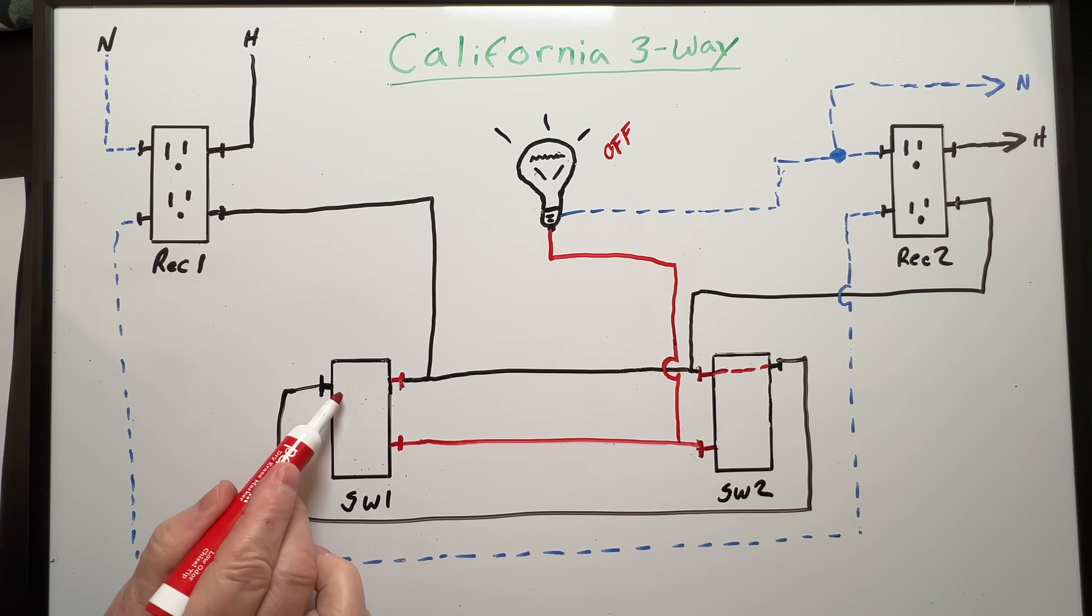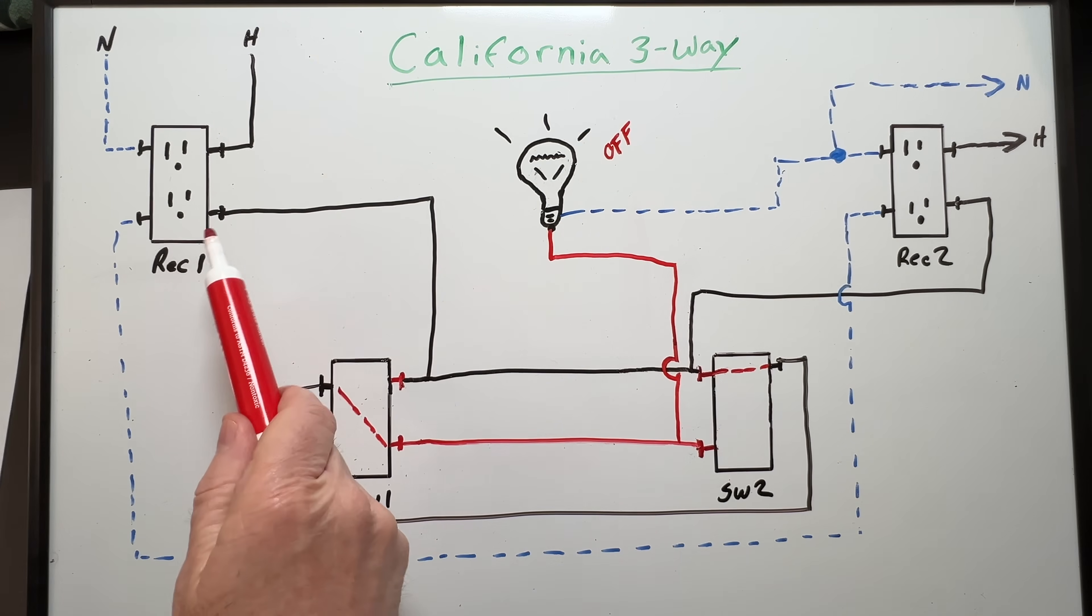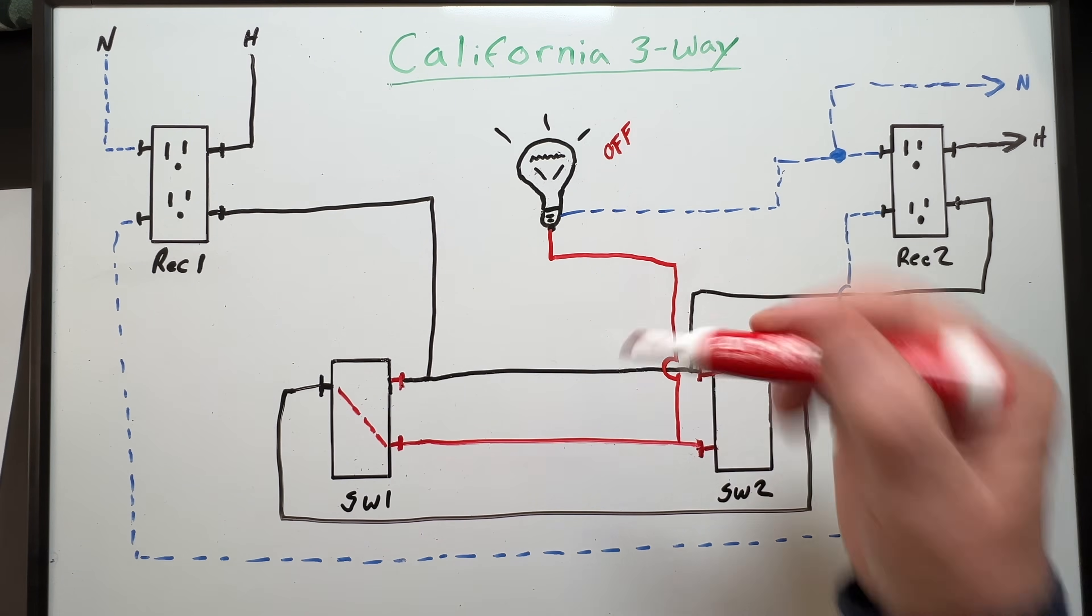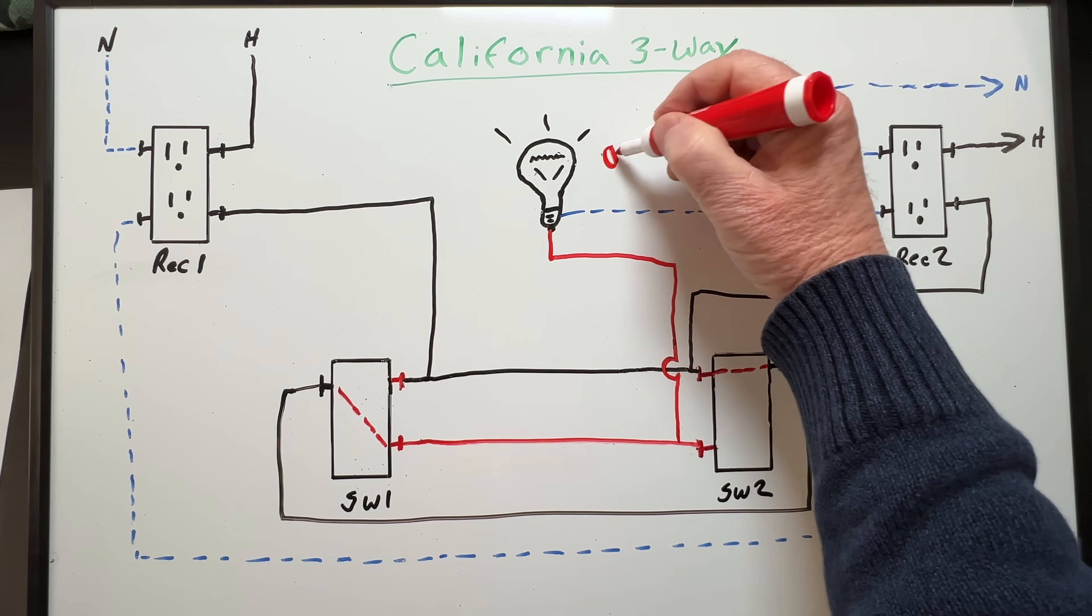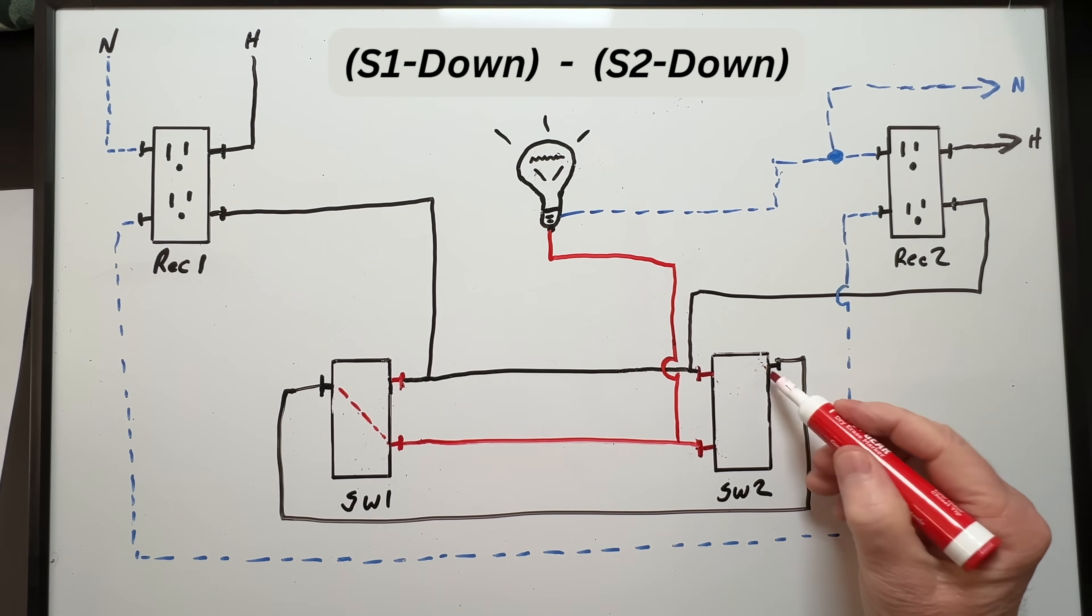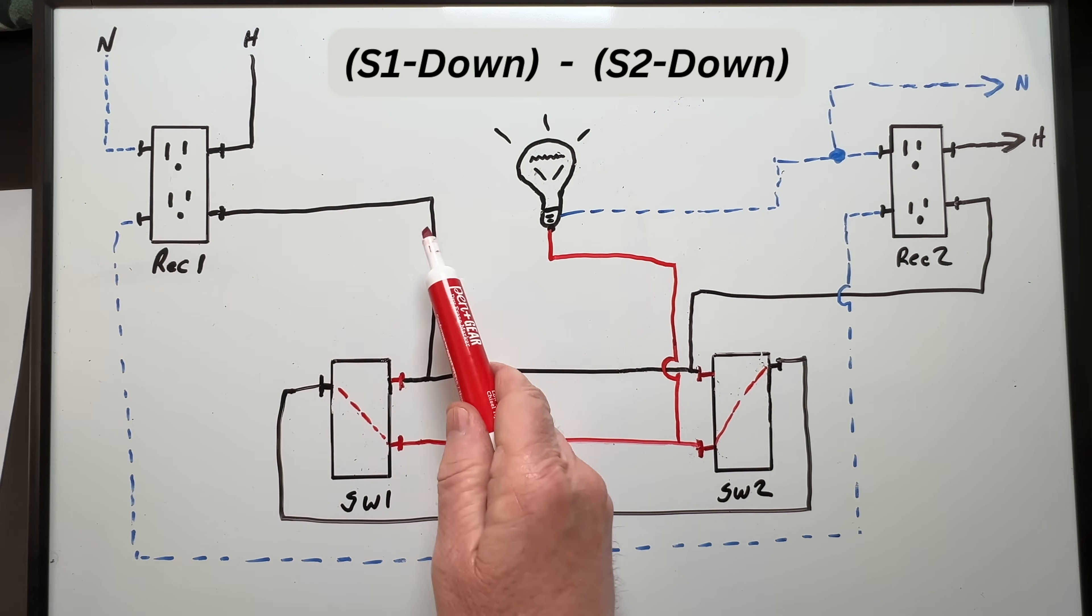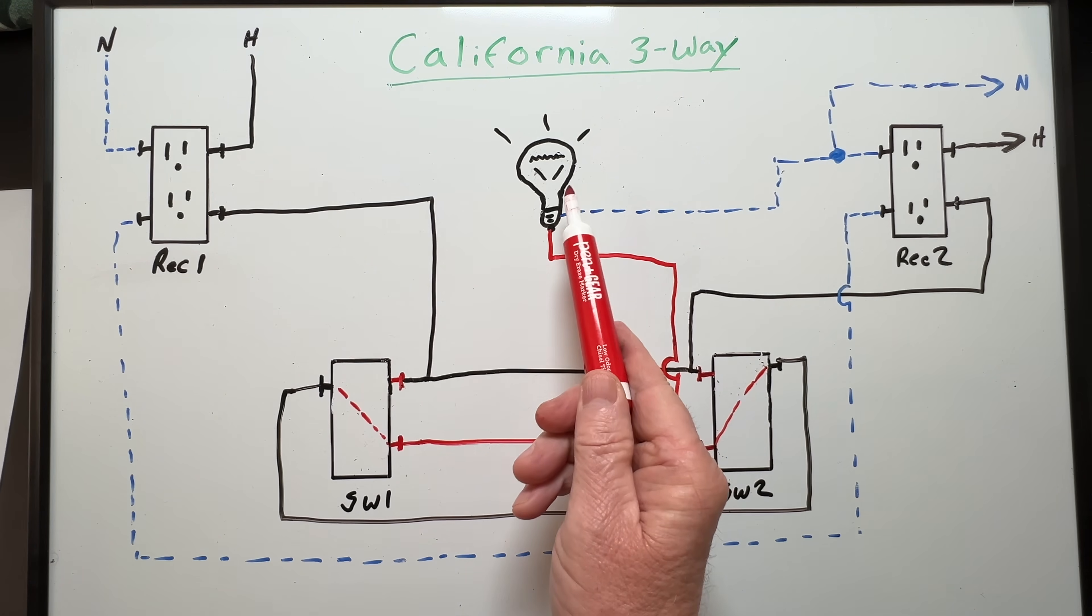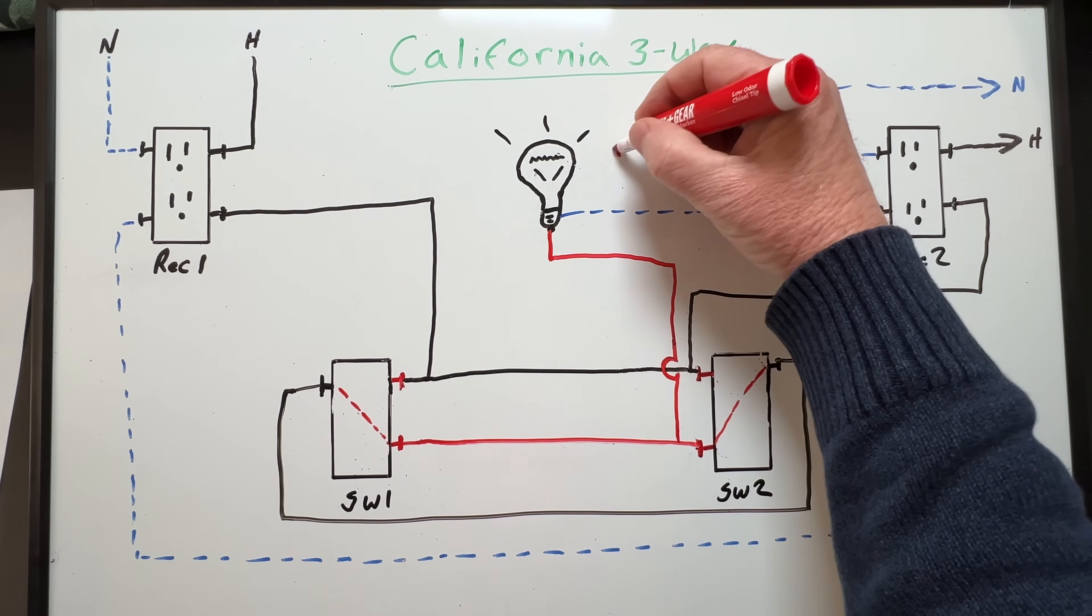Now let's move switch one to the down position. This time our power comes down from our receptacle to switch one goes across to switch two through switch two across our black wire to common on switch one across switch one over and then up to our light. The neutral returns the current again so now our light will be back on. Now let's move switch two to the down position. This time our power comes from receptacle one down to switch one can't get across switch one goes across to switch two can't get across switch two so there is no path to our light. So again our light will be off.